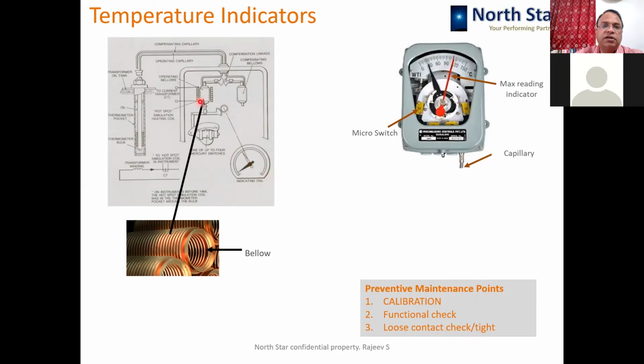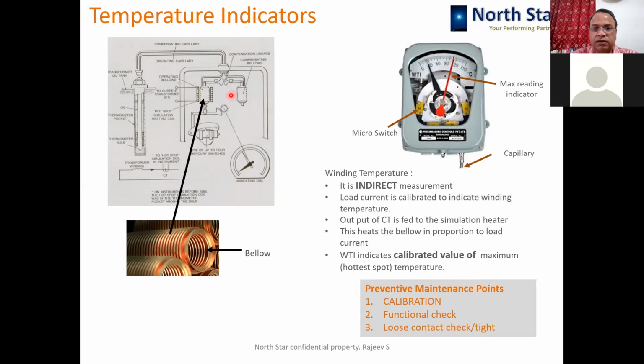In WTI, you have an additional heater, which is fed by the output of the WTI CT, which is put on the terminals, most probably LV or HV also. So the current in the heater is proportional to the load on the transformer. The heat generated around the bellow is proportional to the load, and that's how you calibrate the meter to indicate the winding temperature. So it is not a direct reading, it is an indirect measurement. It is also called the thermal image.